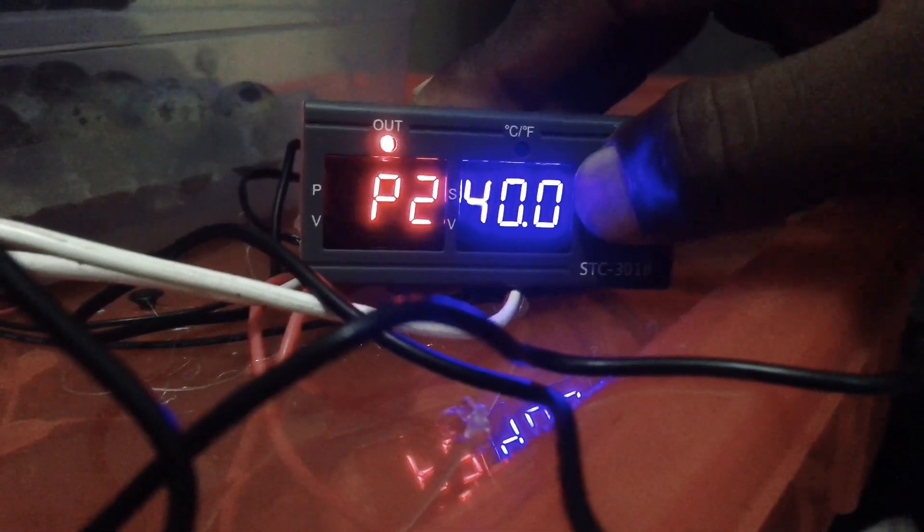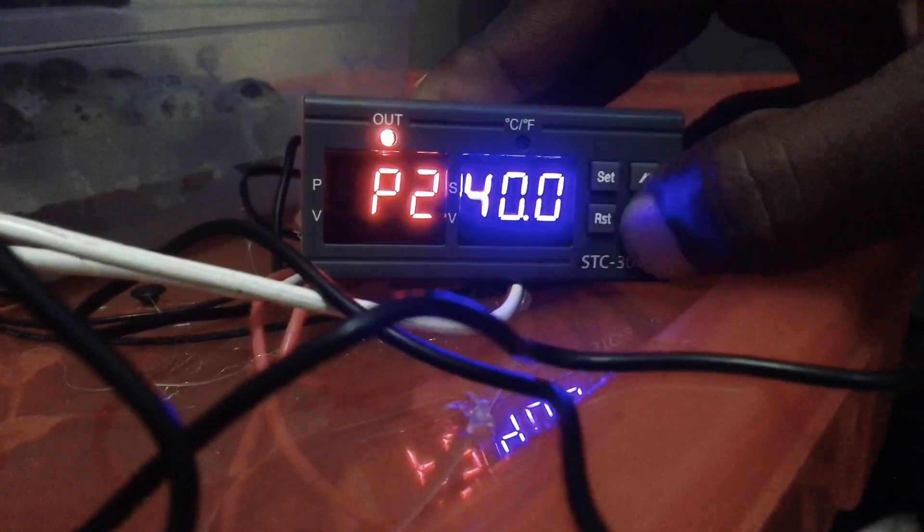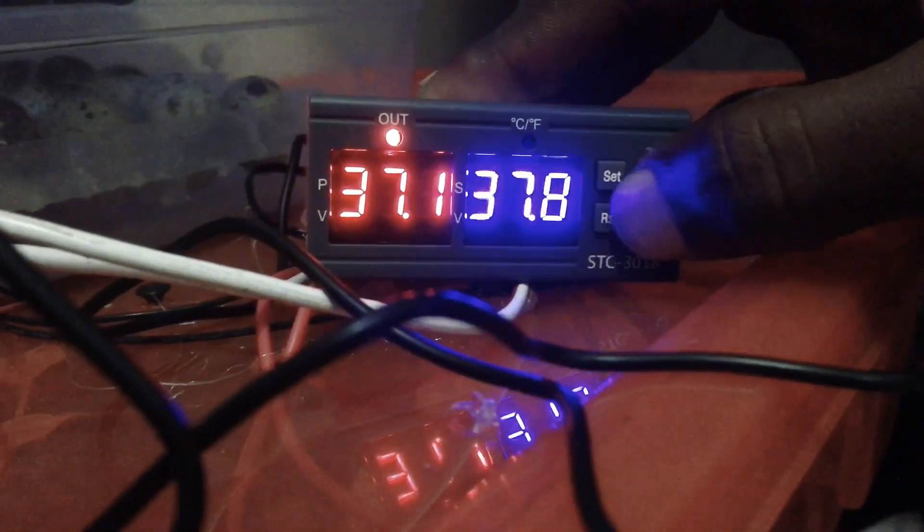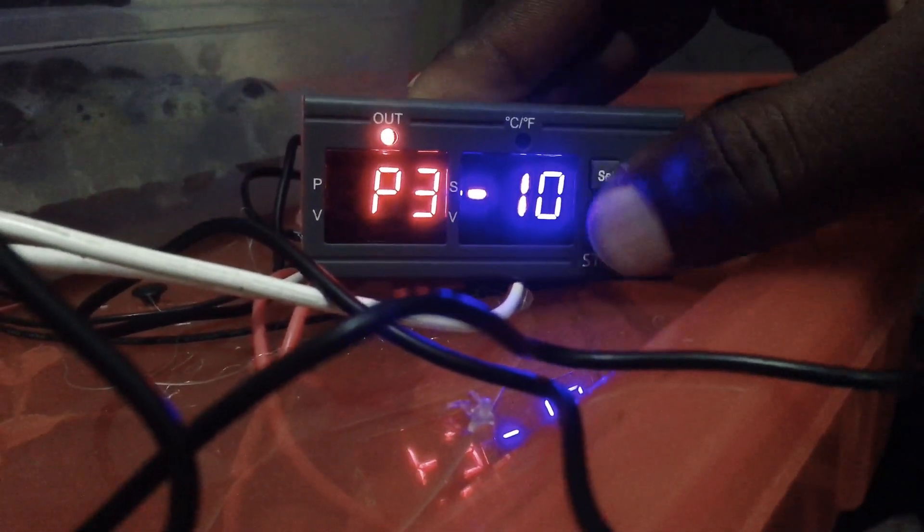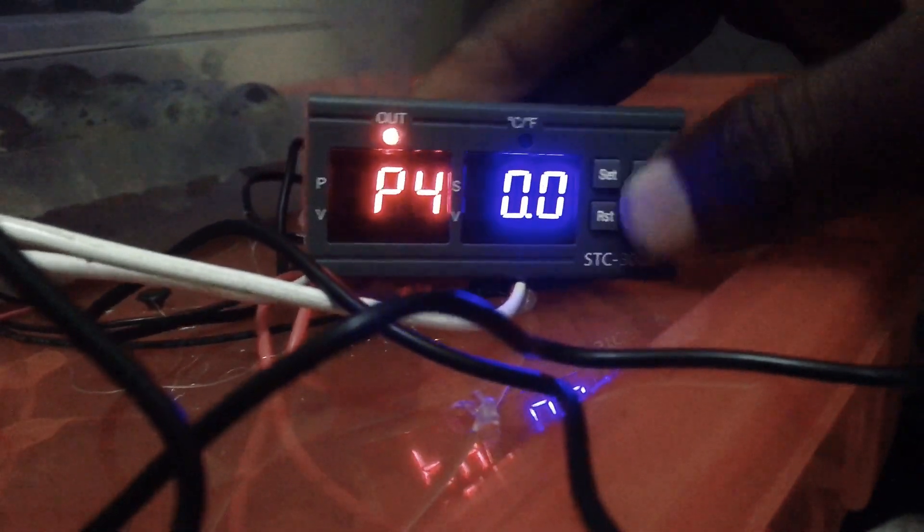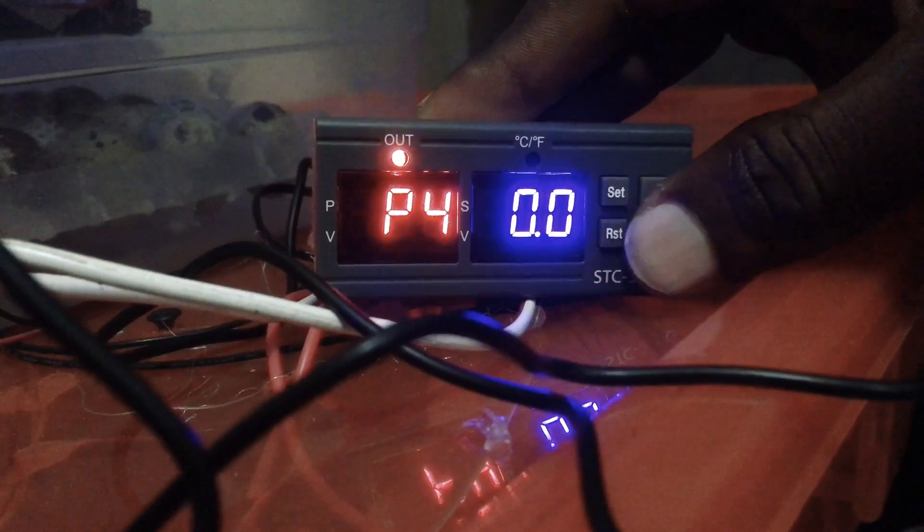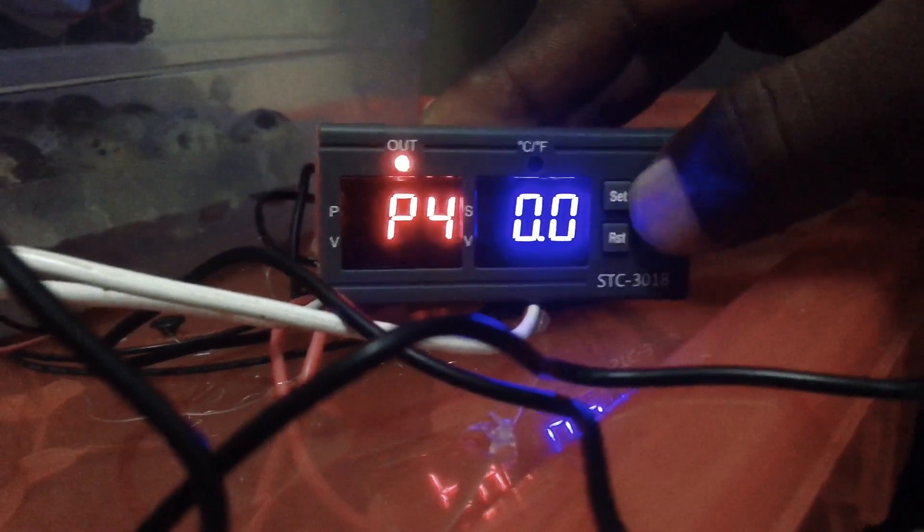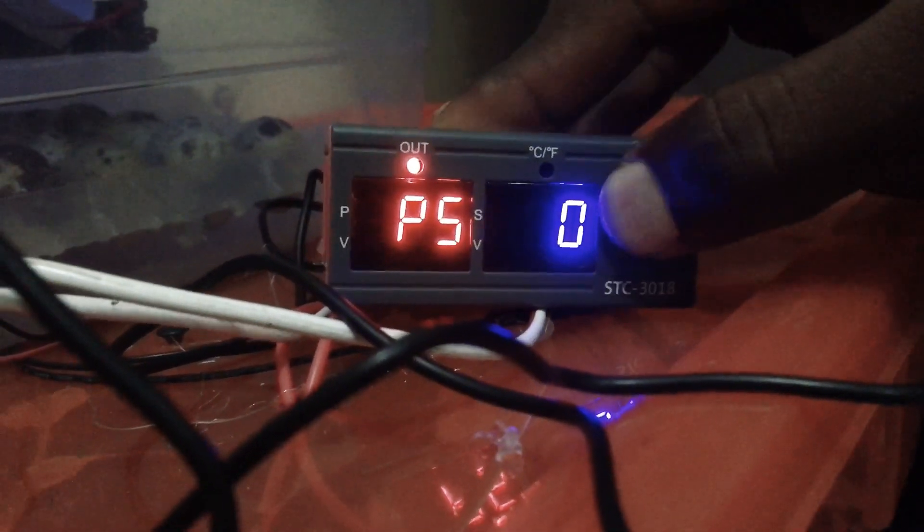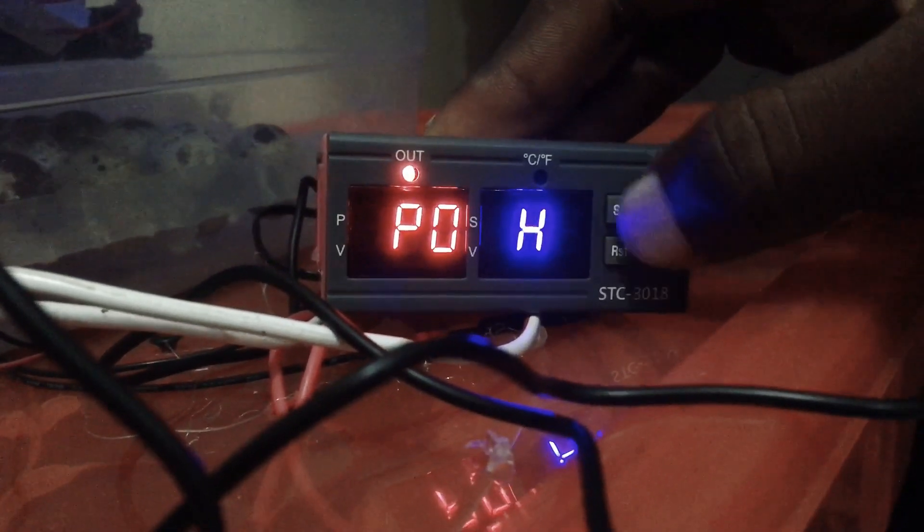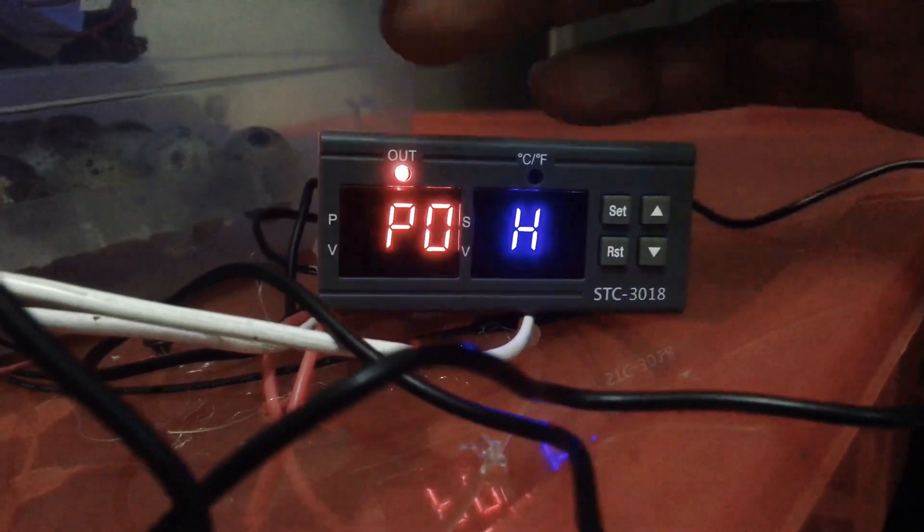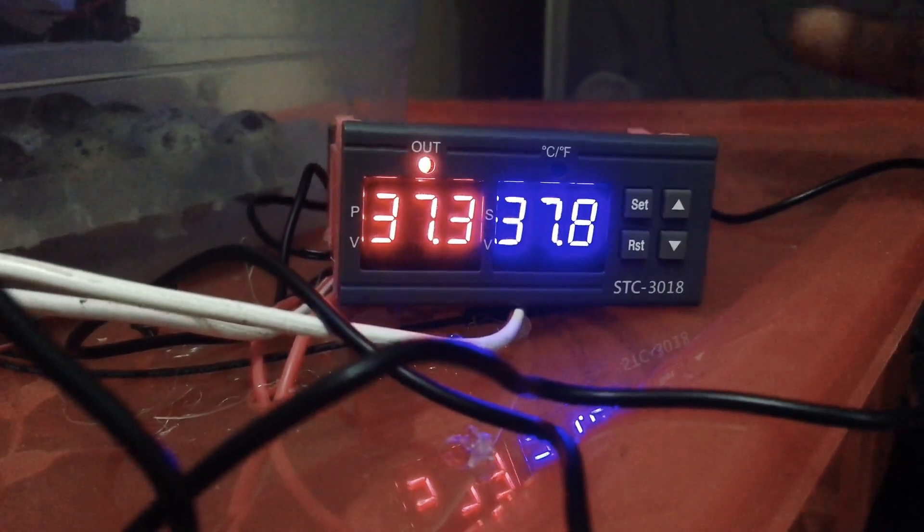So P2 should be 40.0. You press set again for P3. P3 should be minus 10. Press set again, you move it. P4 should be 0, P5 should be 0, P6 should be C. Then you come back to P0 and that's it. You leave it then it goes back to its side.